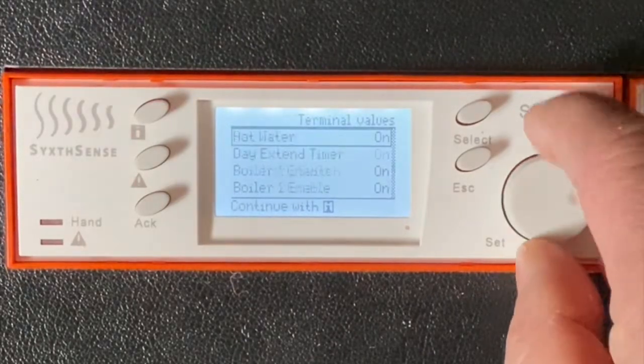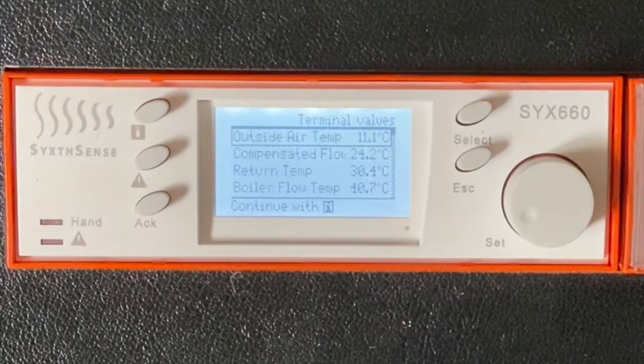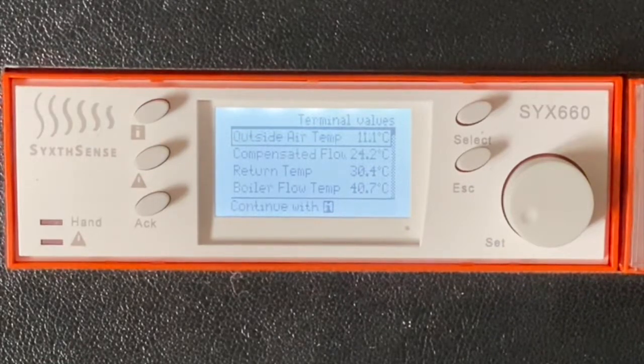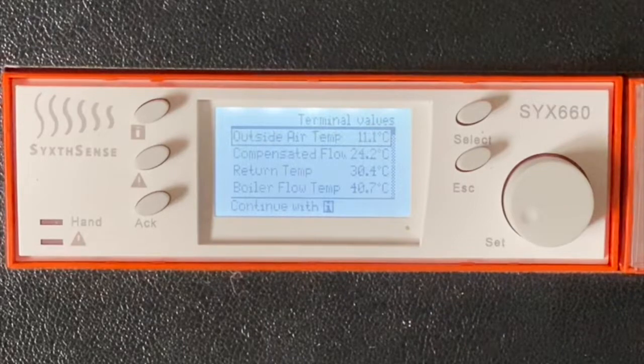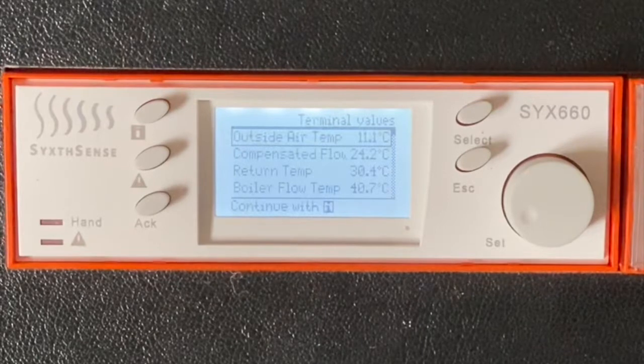So it's a good point to start, just look at the pins, see what the current condition is before you start to get too involved in trying to work out why things are or aren't working. Sensors, all the sensors should be reading, obviously the ones that are connected. For certain applications we need certain sensors connected, so just make sure that they're all wired in correctly. Some of the controller types do have polarity sensitive sensors, so on the SYX660 product, the sensor connections are polarity sensitive, so you must observe the correct connection of the sensors. All the other controller types are not polarity sensitive, and it doesn't matter if they are incorrectly wired. There's no damage you can do to the actual sensor inputs by wiring them the wrong way around.